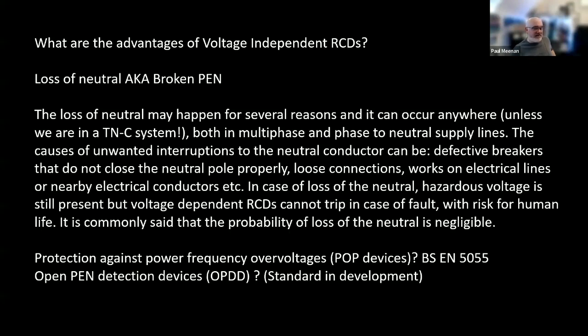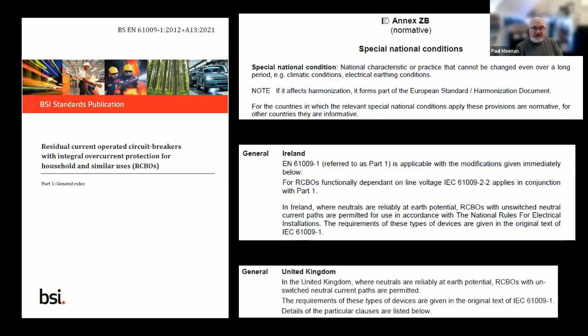Power against overvoltage protection devices could be an answer. OPEN devices could be an answer. In the UK, people are exploring that and very successfully exploring it. So it's still an exciting journey we're on as to how we select and erect best. But one bit of advice, please check in your standards for the special national conditions in the appendix. So this is BS EN 61009. That's a combined MCB RCD with overcurrent protection. And it has some special conditions that say in Ireland, 61009s, dependent on line voltage, can be used. You can use unswitched neutrals. In the UK, where neutrals are reliable at earth potential, RCBOs with unswitched neutral are permitted.